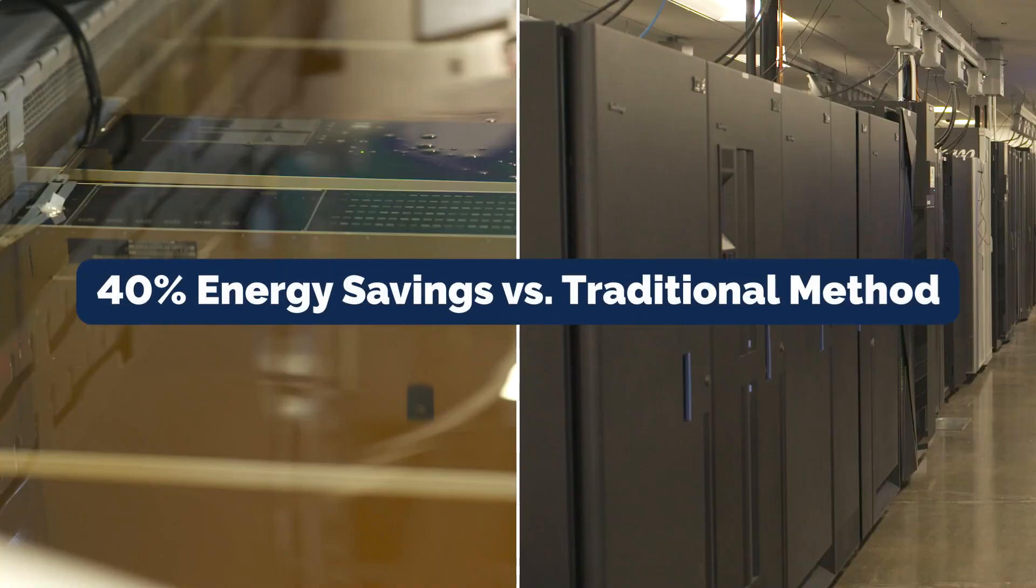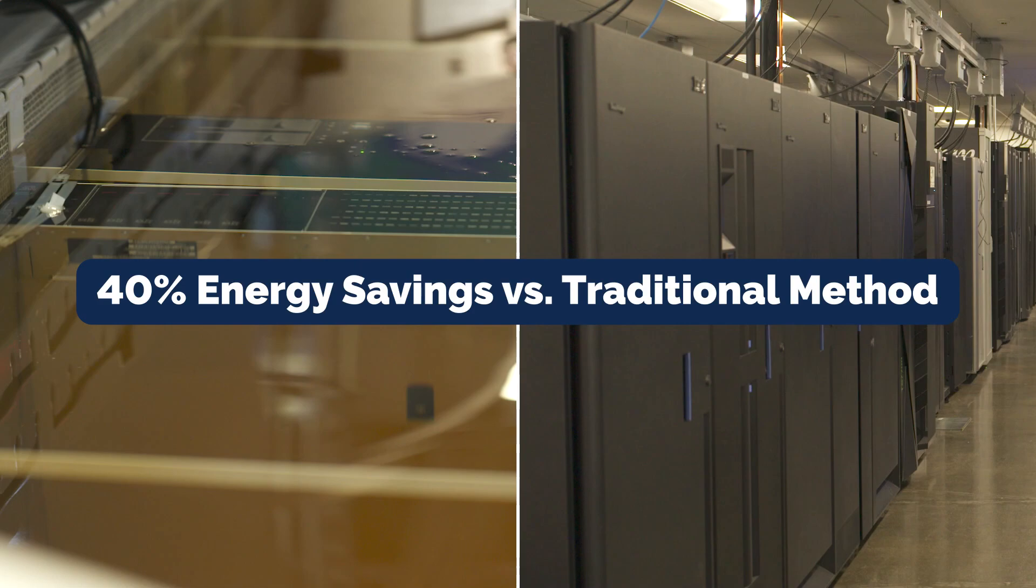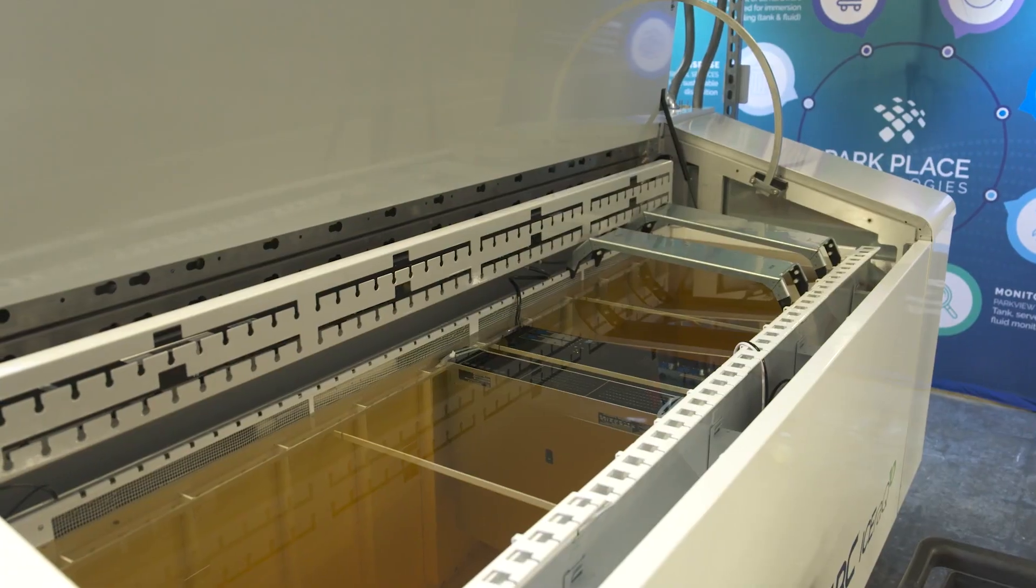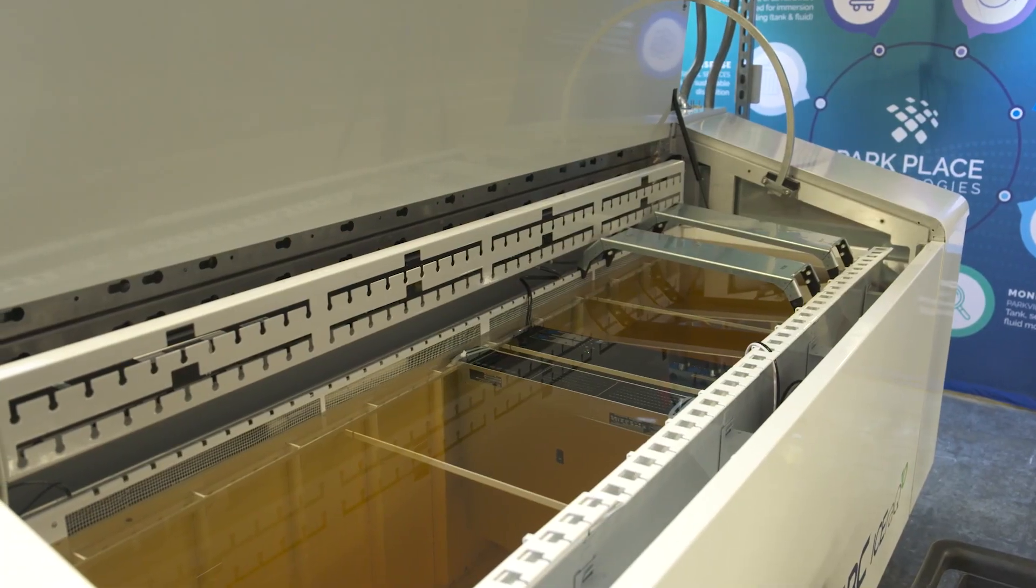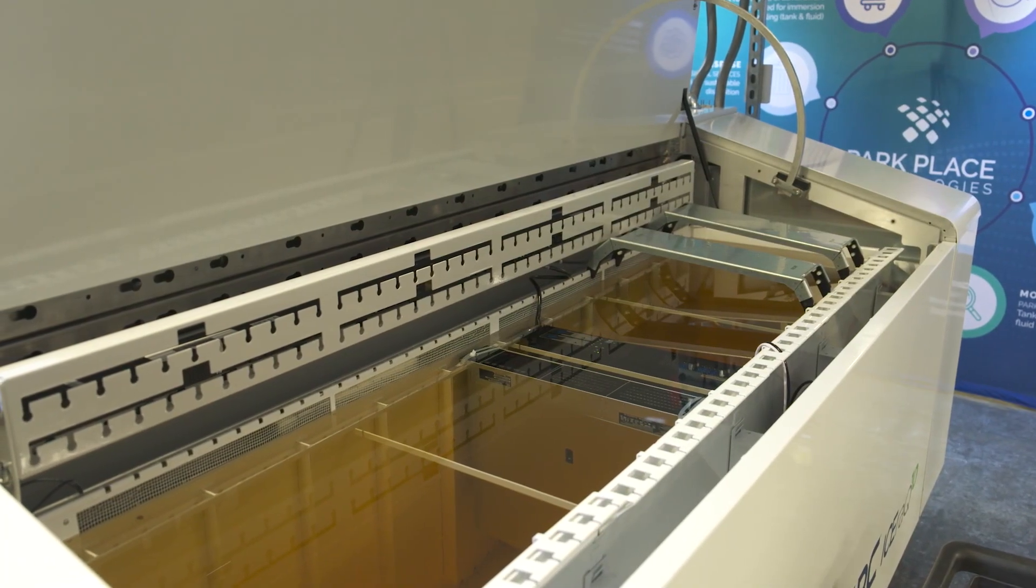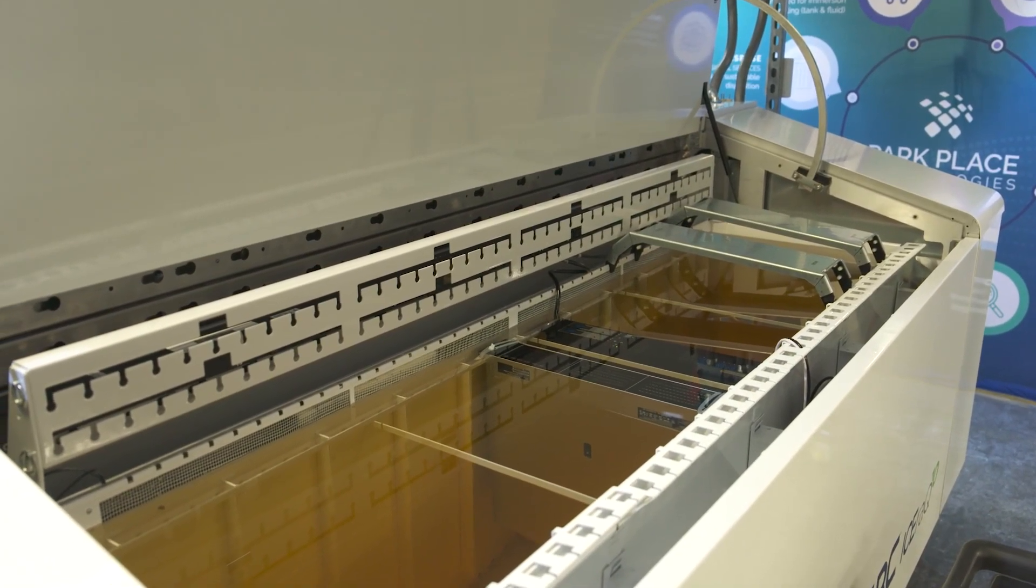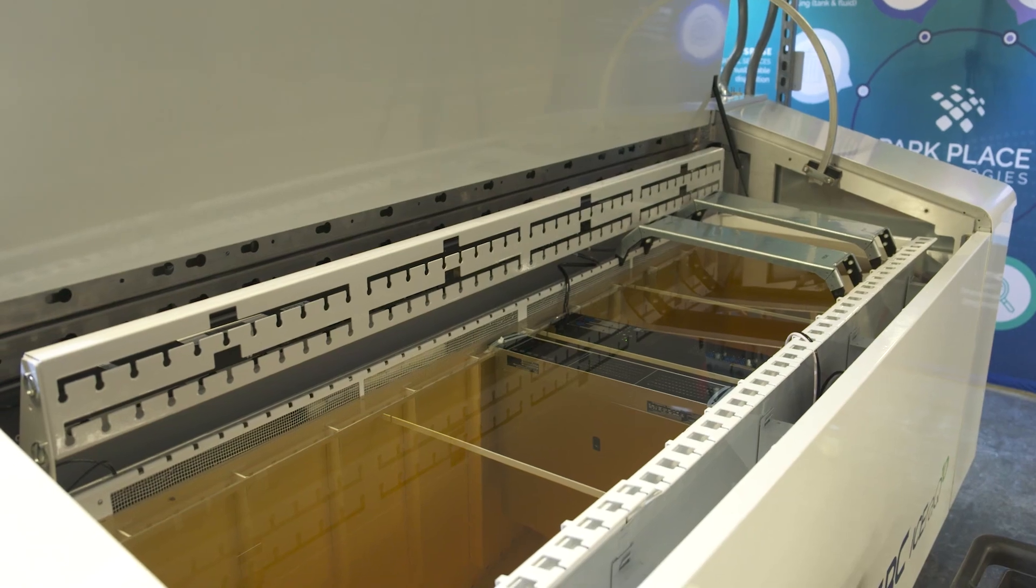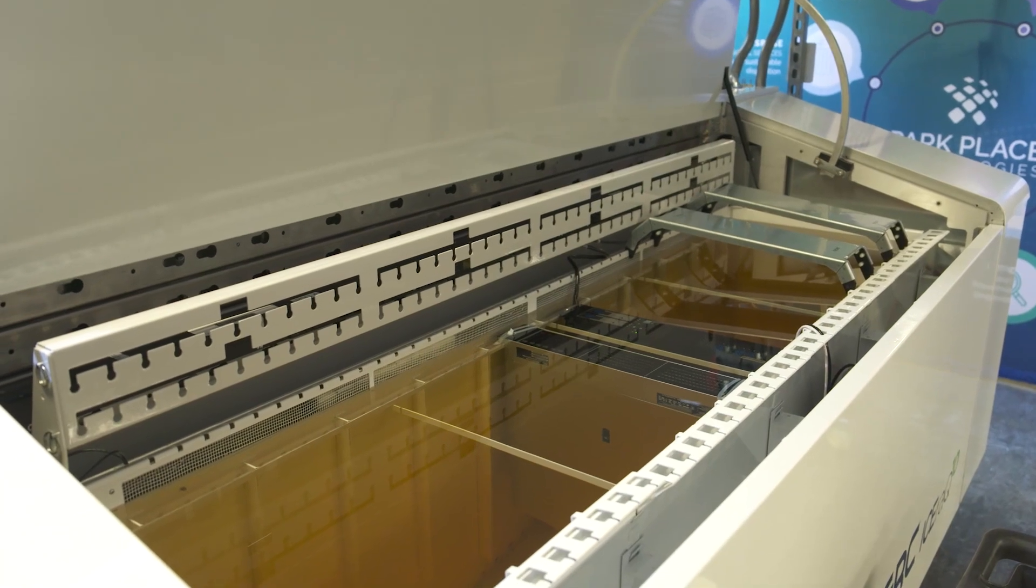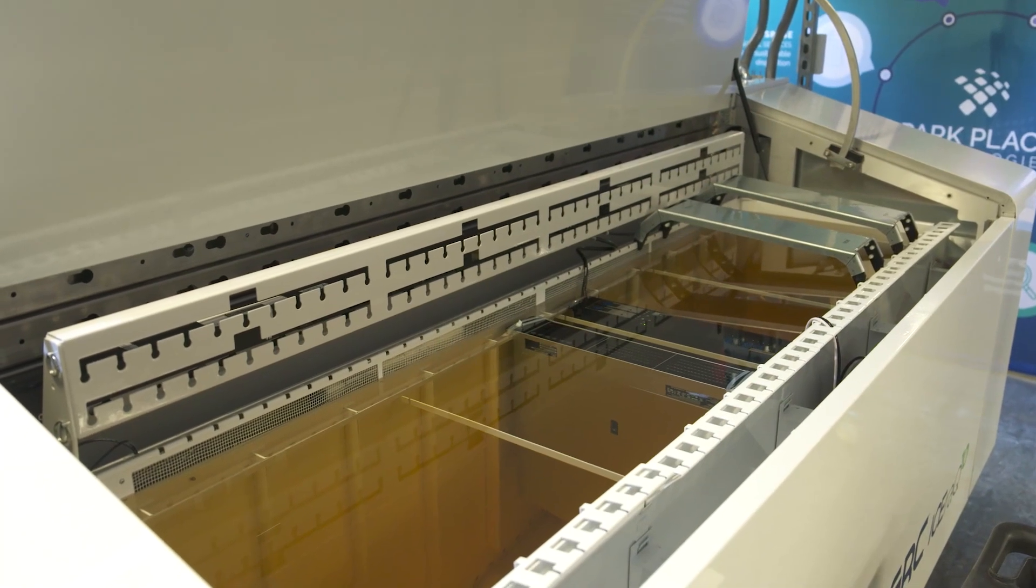You save about 40 percent of energy using liquid immersion as opposed to traditional data center cooling methods. One of the second benefits is the rack density. You can squeeze about 10 times the amount of compute in the same physical space as you would in a traditional air-cooled data center.